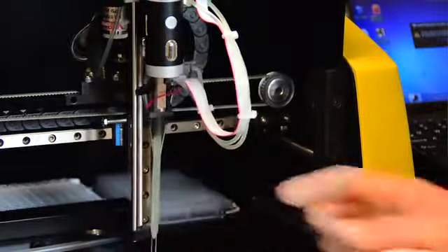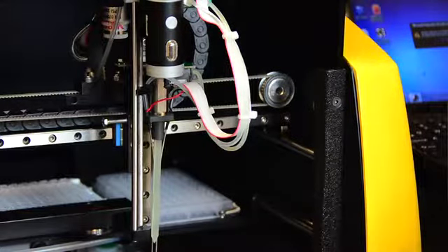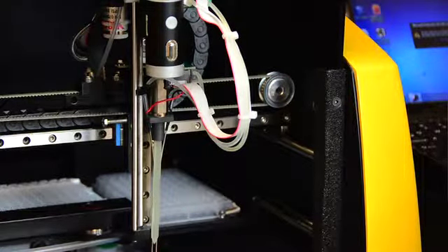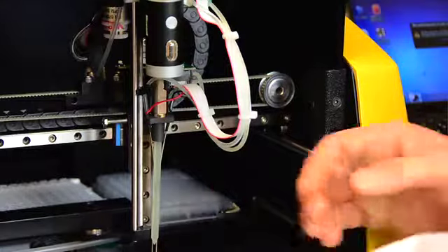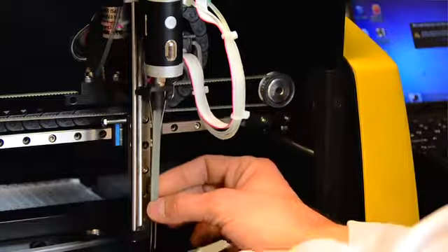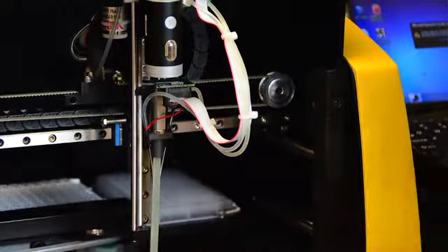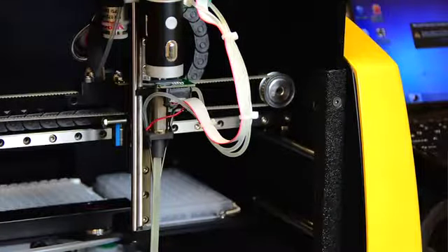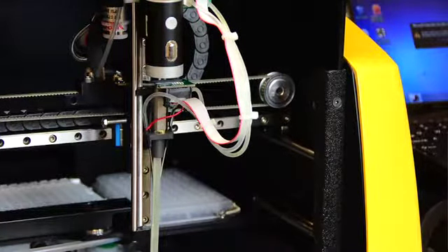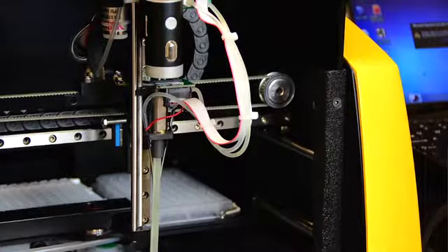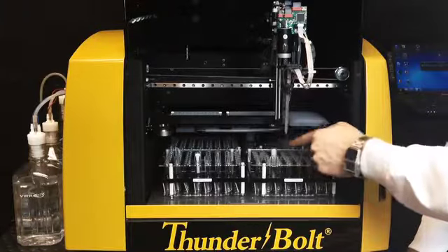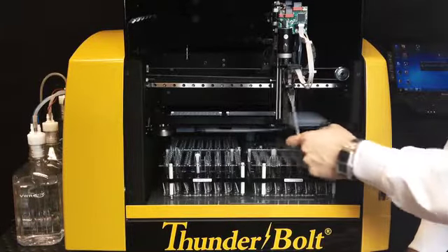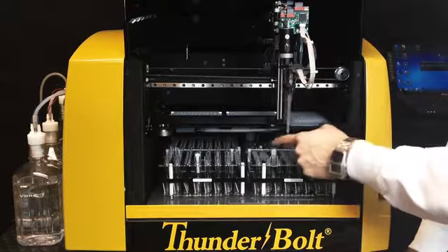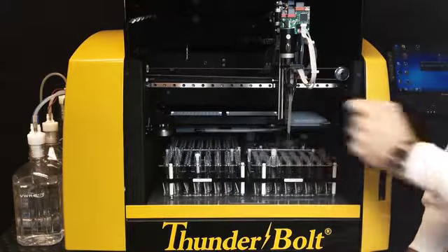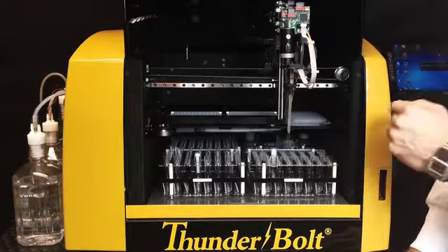So what I like to do with customers is I'll often show them that the probe is just held down by the force of gravity on a rail. So it's hard to break the probe, and it's hard to break other things with the probe. You won't pierce your hand, you won't break a tube, you don't have to worry about those other things that actually, with other instruments, you should be concerned about. The other thing, like I mentioned earlier, is that the probe is held on by a magnet. So if it gets struck in the horizontal plane, it'll just snap back into location.